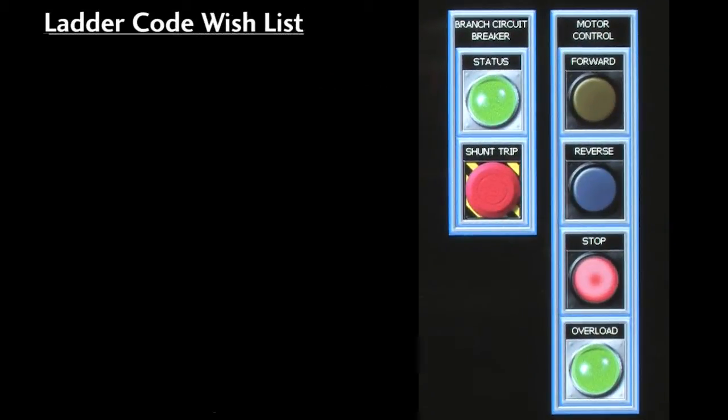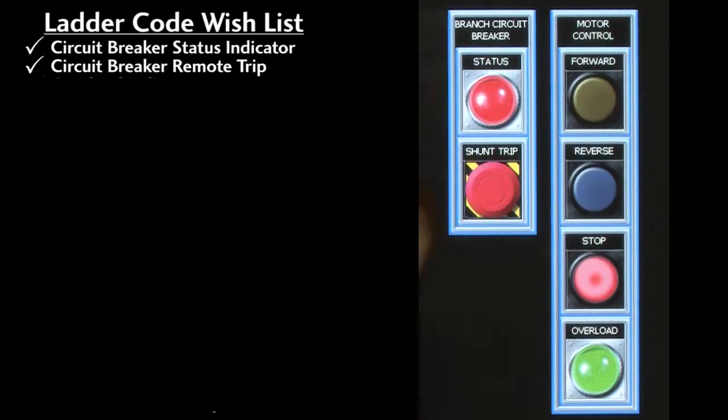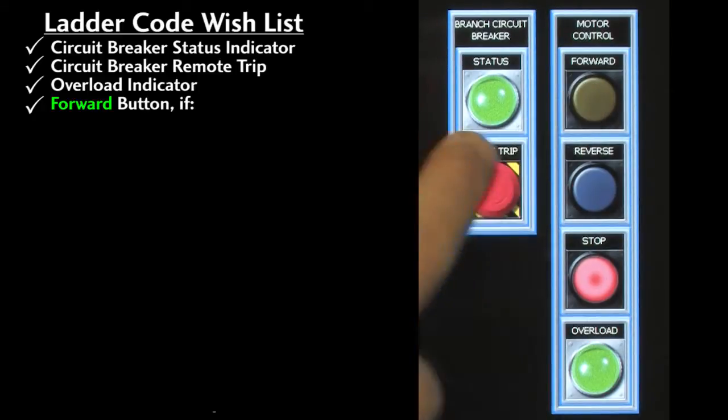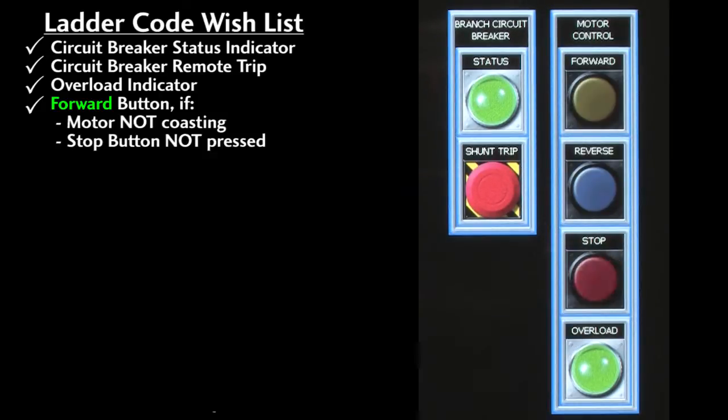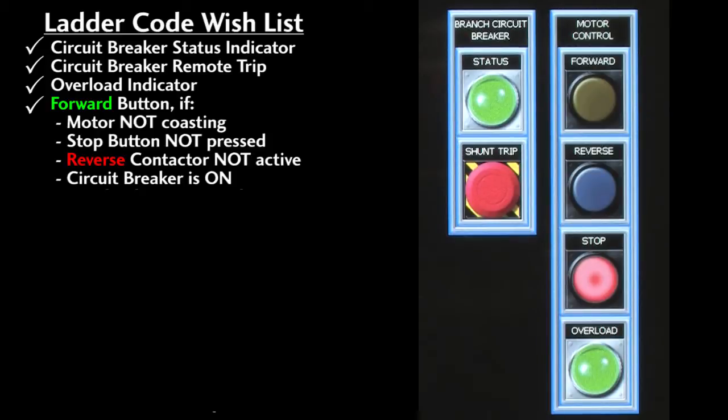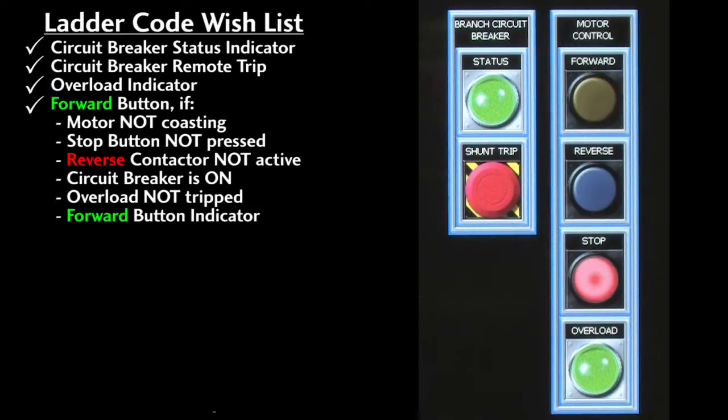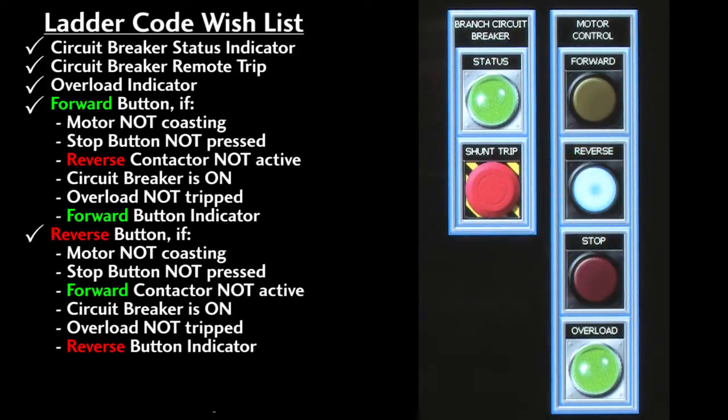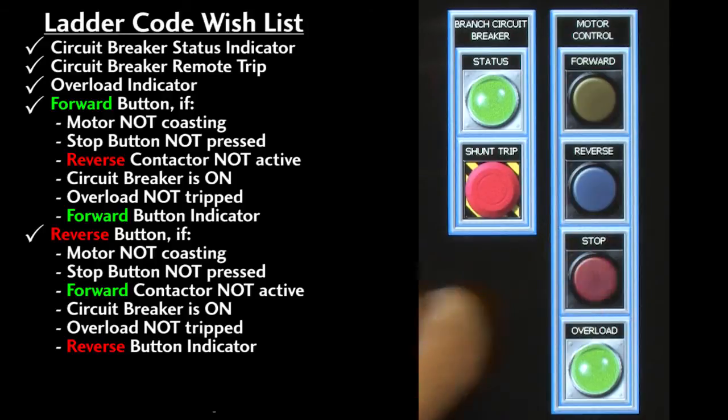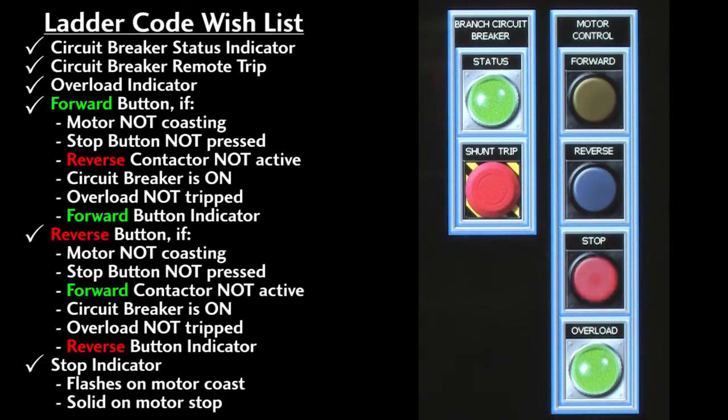Here's our ladder code wish list. We want a circuit breaker status indicator, we want to be able to trip the circuit breaker on a button press, we want an overload indicator, and on the forward button press we want to start the motor in the forward direction if the motor is not coasting, if the stop button is not being pressed, if the reverse contactor isn't engaged, if the circuit breaker is on, if the overload is not tripped, and we'll want the forward indicator lit while the motor is running. The reverse button has the exact same requirements except it doesn't start the motor if the forward contactor is engaged. We want the stop indicator to flash when the motor is coasting and to be on when the motor is stopped.